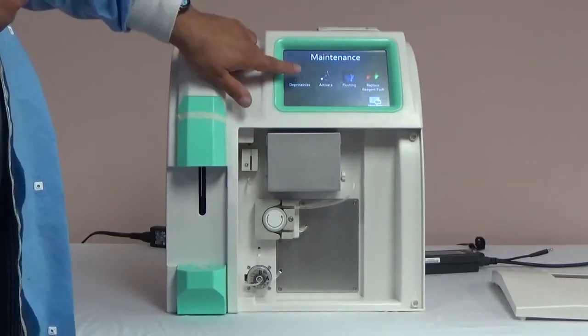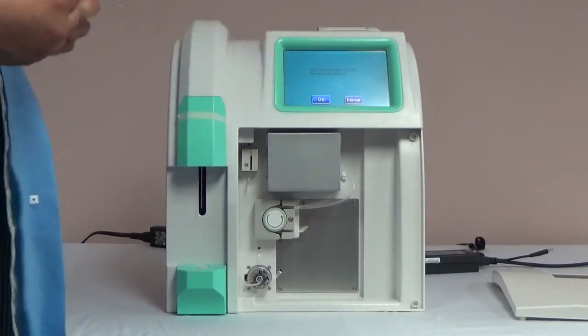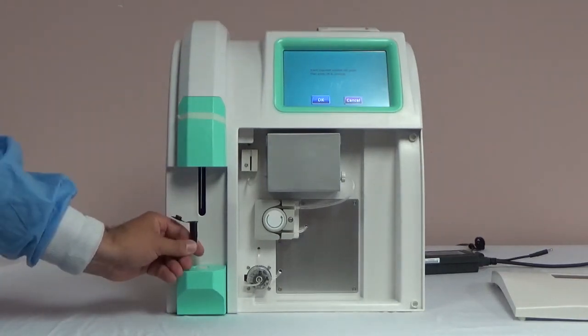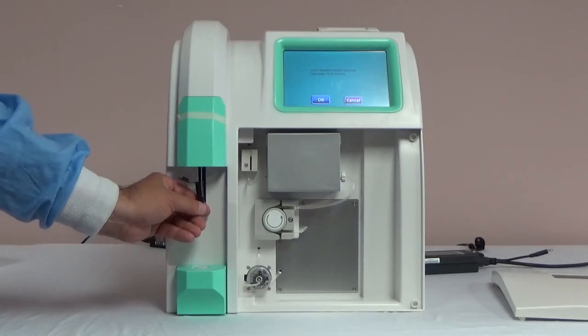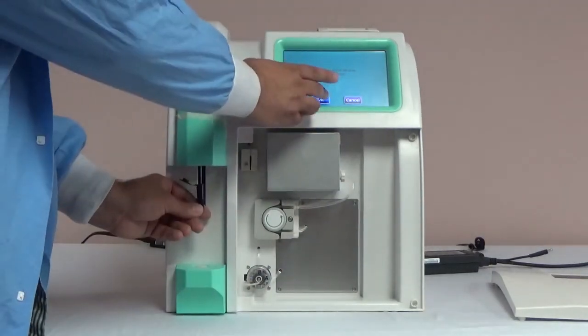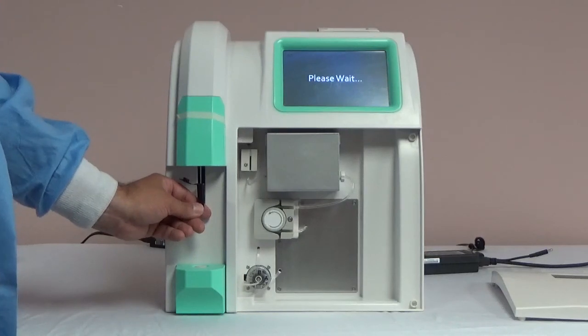After 5 minutes, begin the deproteinization process by selecting maintenance from the main menu, followed by deproteinize. The analyzer will ask you to insert the solution into the probe. When you insert the solution, do not push it all the way to the bottom of the vial. If you put the probe too close to the bottom, the probe will not be able to aspirate enough solution. Once it aspirates, the analyzer will tell you to remove the solution and it will run the process.